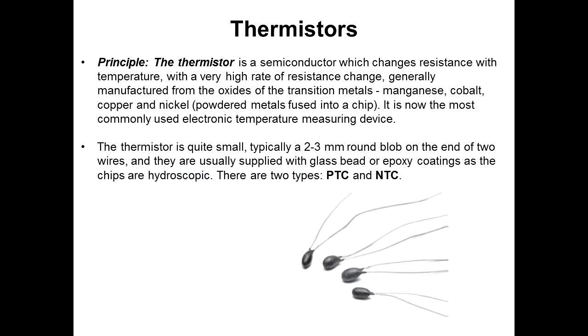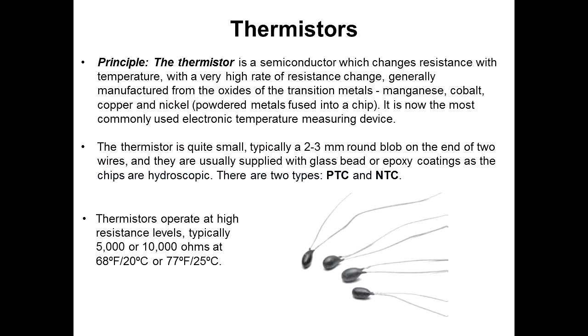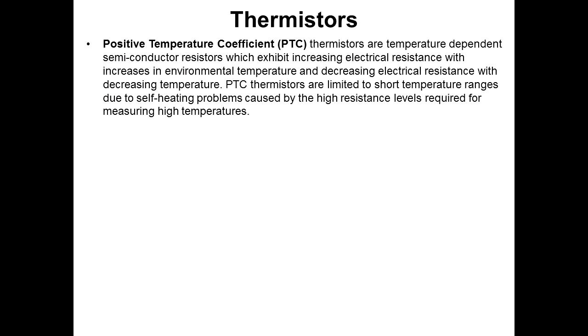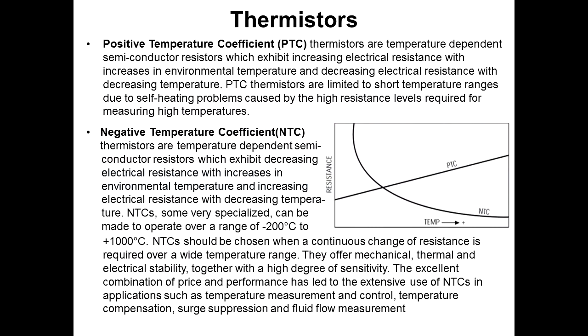The chips made from this powder are very highly hygroscopic and will absorb water like crazy. There are 2 types, PTC and NTC. They typically operate at 5 or 10,000 ohms of resistance at 2 standardized temperatures. However, many people use their own curves, so there aren't very many standardized curves in the industry for thermistors. Positive temperature coefficient: as the temperature went up, the resistance went up. Since they operate at very high resistance levels, they tended to get very hot, so you had to deal with the self-heating problems caused by that higher level of resistance. With NTCs, negative temperature coefficient, temperature goes up, the resistance goes down, so you don't have to deal with the self-heating issues.